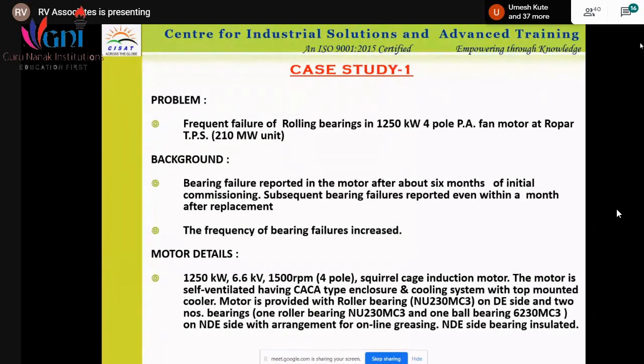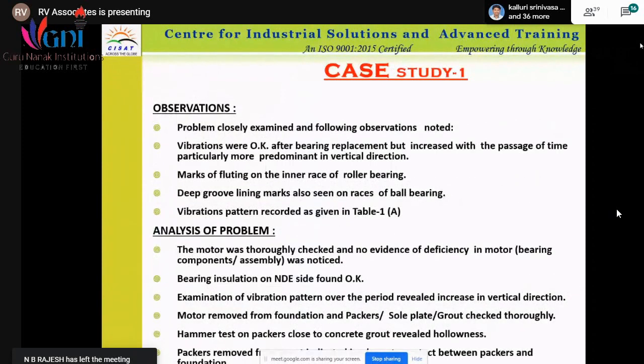Similarly, case studies are there for the transformer, like motor failure. Whatever the analysis is, it shows that most of the time the bearing fails. Why does the bearing fail? Because the coupling is not proper. Whatever the drive end and the load are, they have not been connected parallel; there is some slight change in the degree. So it gives an imbalance, which will lead to the failure of the bearing. Like that, many case studies are there. Every time, based on the observations, various problems have been analyzed and are to be corrected.